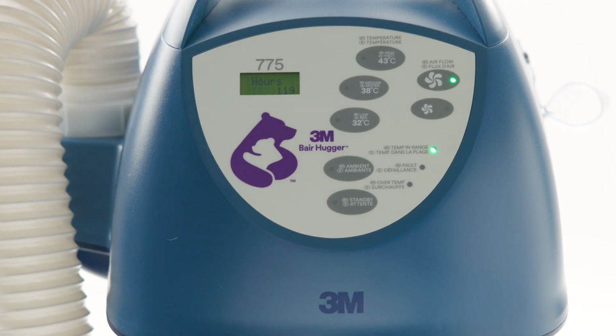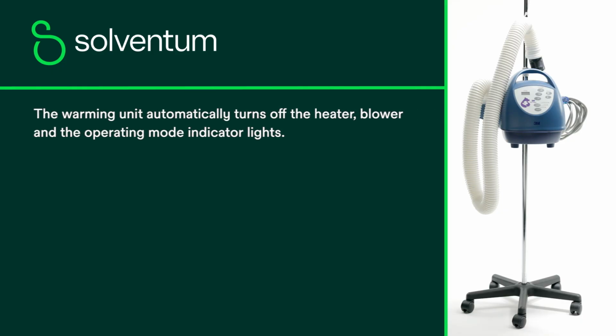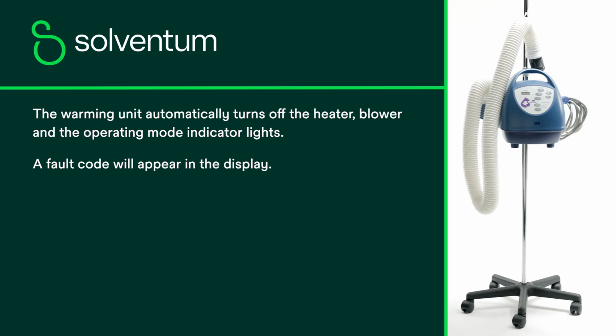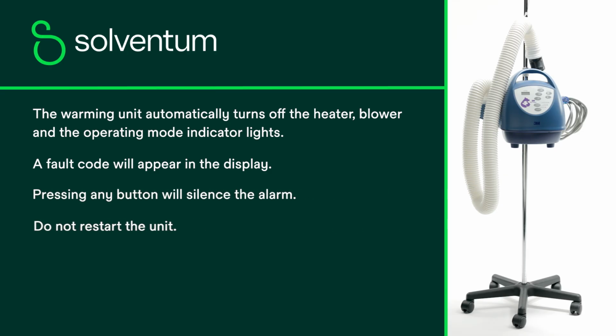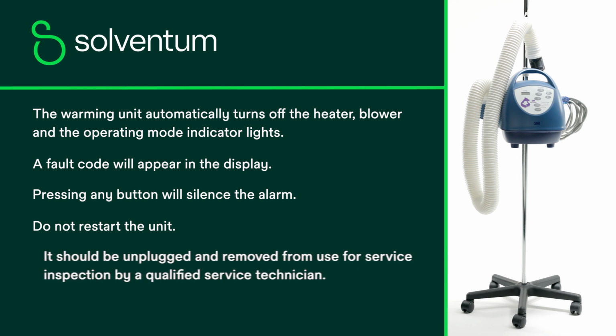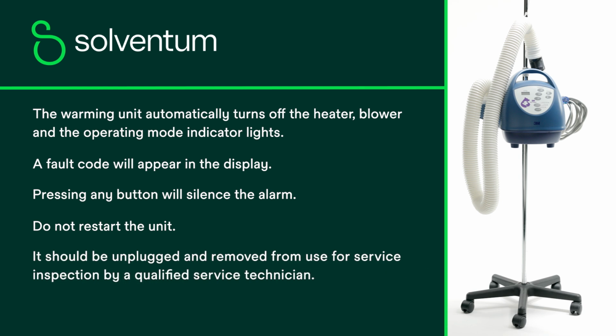If an overtemperature condition occurs, the red overtemp indicator light flashes and an audible alarm sounds. The warming unit automatically turns off the heater, blower, and the operating mode indicator lights. A fault code will appear in the display. Pressing any button will silence the alarm. Do not restart the unit. It should be unplugged and removed from use for service inspection by a qualified service technician.